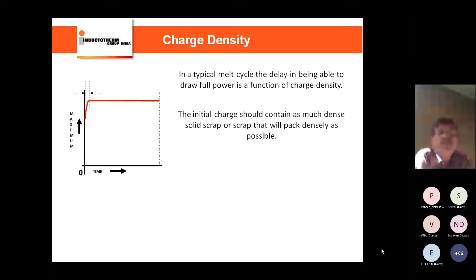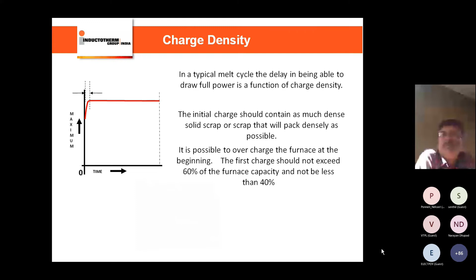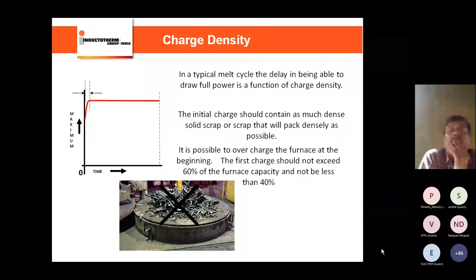Now coming to scrap efficiency, E2. The main point is the charge density. In a typical melt cycle, the delay in being able to draw full power is a function of charge density. The initial charge should contain as much dense solid scrap, or scrap that will pack densely, as possible. It is possible to overcharge the furnace at the beginning. The first charge should not exceed 60% of furnace capacity and not be less than 40%. So charge density is very essential to draw the full power from the beginning. At the same time, one should avoid overcharging above 60% of the furnace capacity.